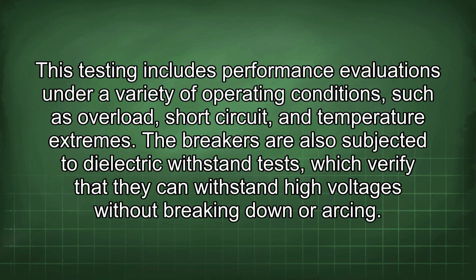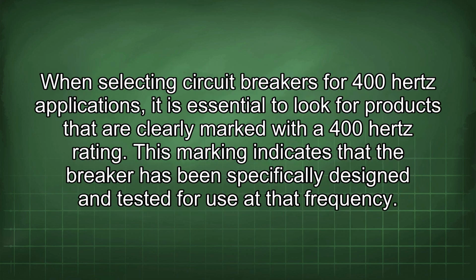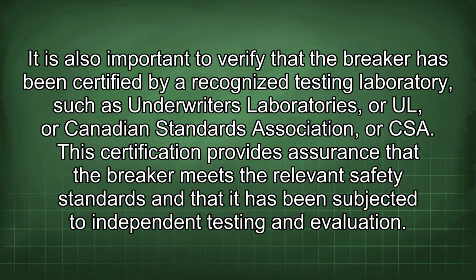down or arcing. When selecting circuit breakers for 400 Hz applications, it is essential to look for products that are clearly marked with a 400 Hz rating. This marking indicates that the breaker has been specifically designed and tested for use at that frequency. It is also important to verify that the breaker has been certified by a recognized testing laboratory such as Underwriters Laboratories, or UL, or Canadian Standards Association, or CSA.